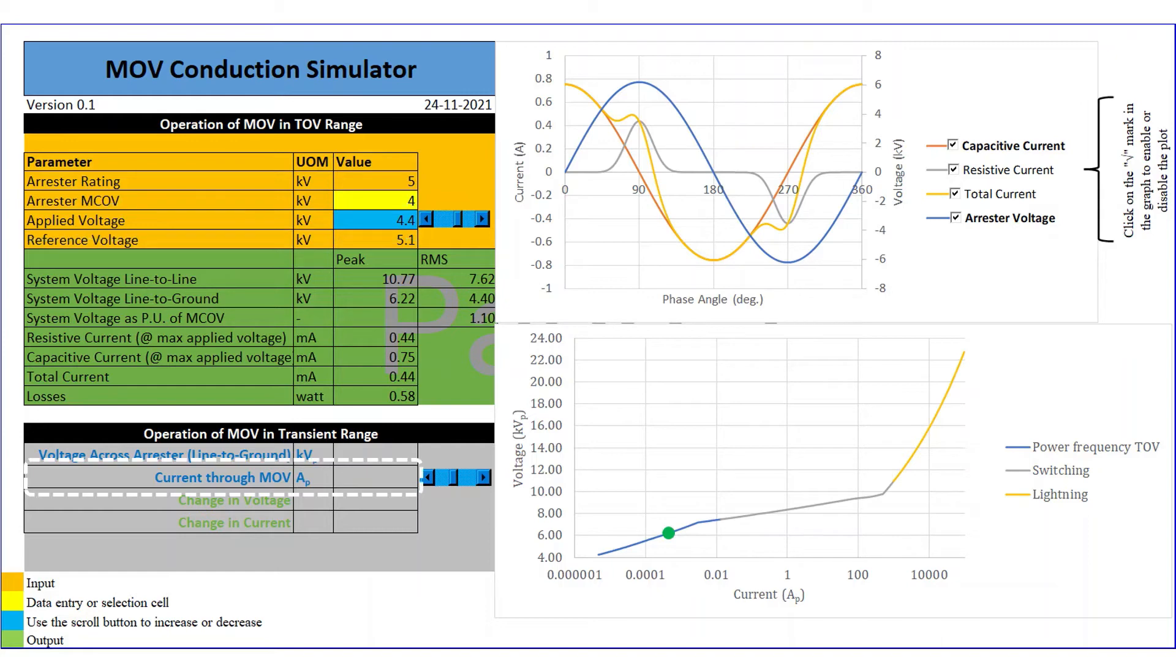The ToV range simulator starts from 3KV till 5.2KV of applied voltage. The transient range simulator starts from 1Apeak till 100kApeak. For the demonstration, we will vary it from 100Apeak till 100kApeak. The residual voltage is also shown in the display. There are two controls, one for the ToV range and other for the transient range.